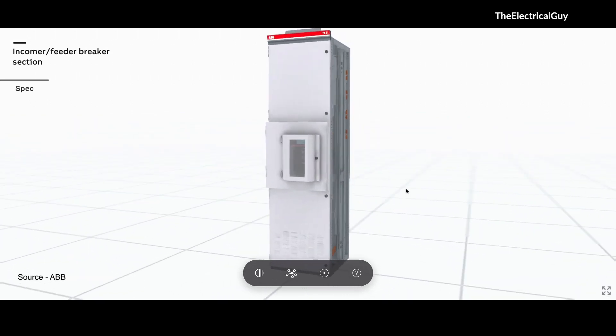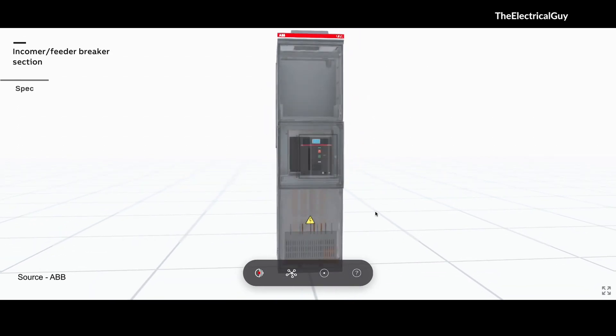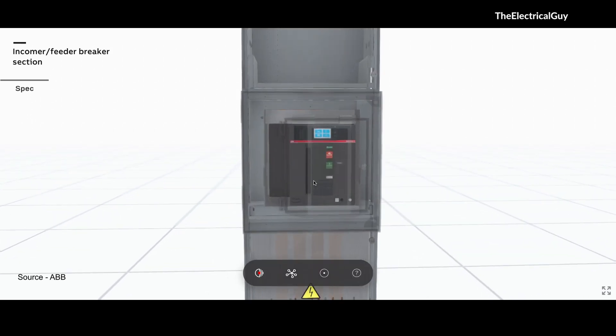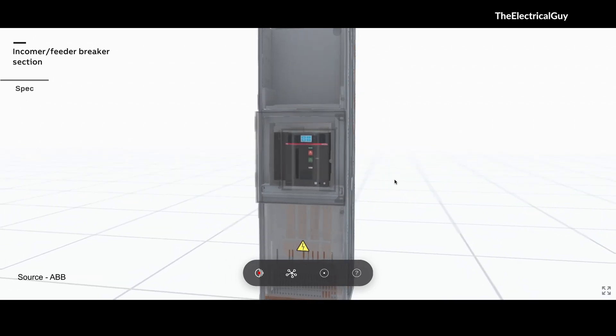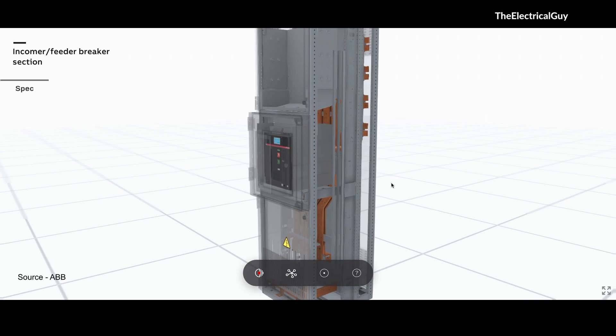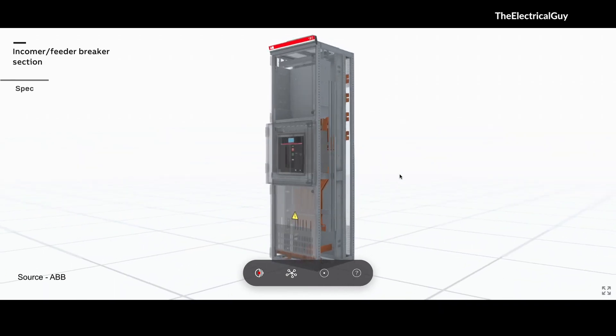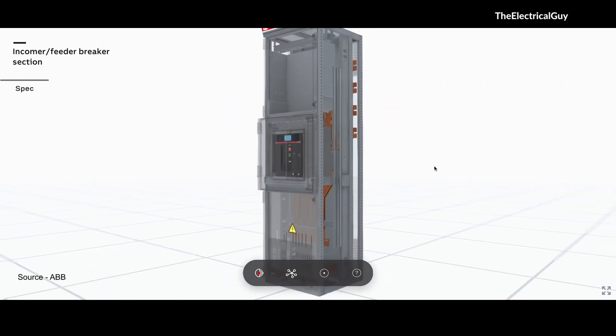This is the breaker section panel, so it majorly has the breaker. Let us see what is inside. So here I am opening the panel. At the center we have the breaker compartment, which is the heart of the panel and a very important component of low voltage switchgear. In low voltage switchgear, we most commonly use an air circuit breaker when we need to rupture high capacity current. Since this is an incomer panel anticipated to carry more current, an air circuit breaker is used here. MCCBs are also commonly used for low voltage switchgear depending upon the current you need to break.